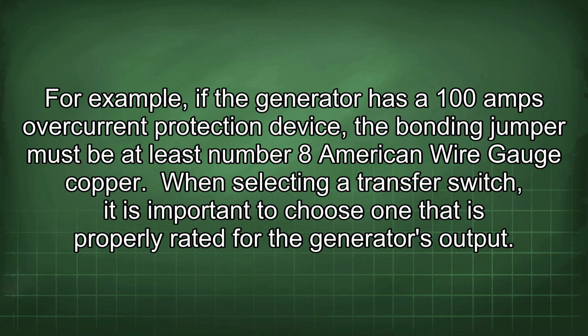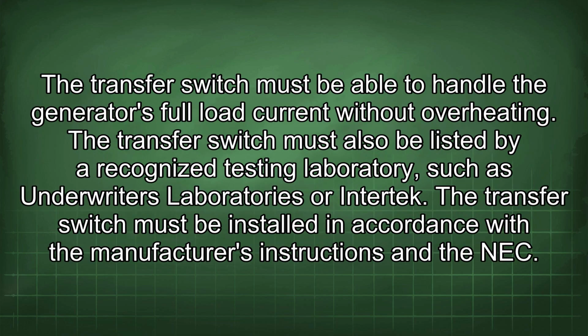When selecting a transfer switch, it is important to choose one that is properly rated for the generator's output. The transfer switch must be able to handle the generator's full load current without overheating. The transfer switch must also be listed by a recognized testing laboratory, such as Underwriters Laboratories or Intertek. The transfer switch must be installed in accordance with the manufacturer's instructions and the NEC.